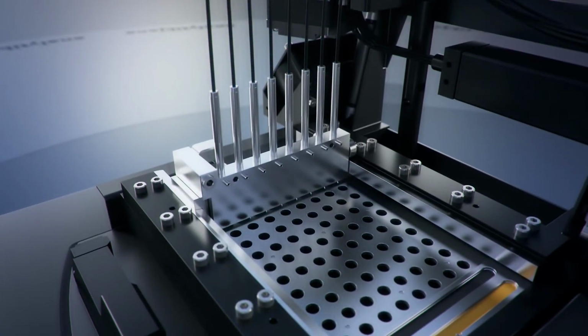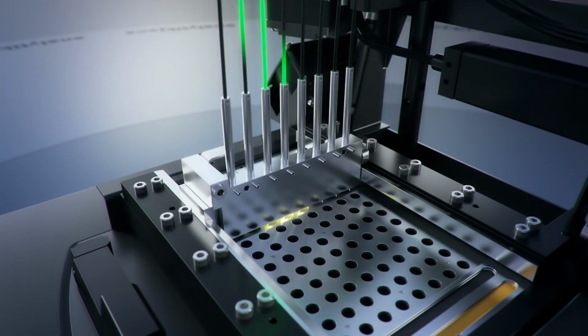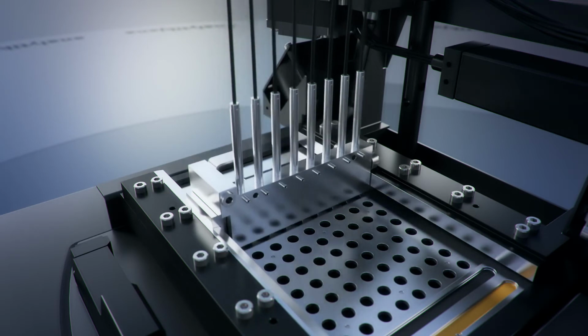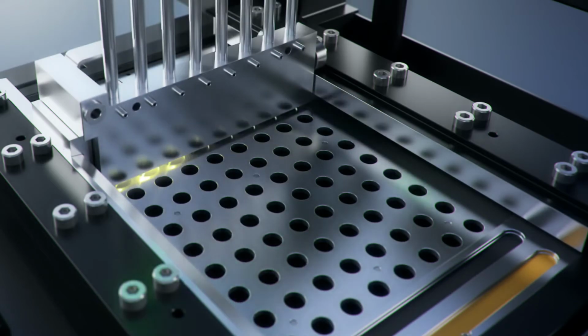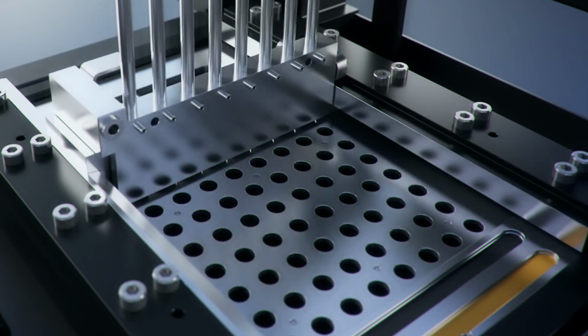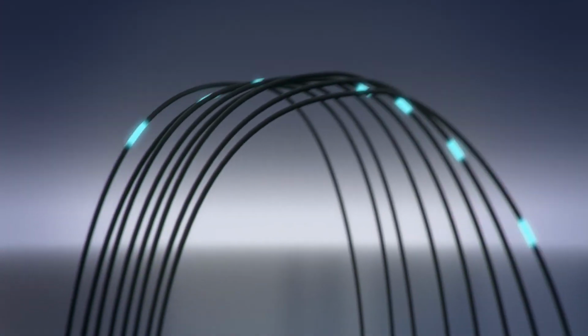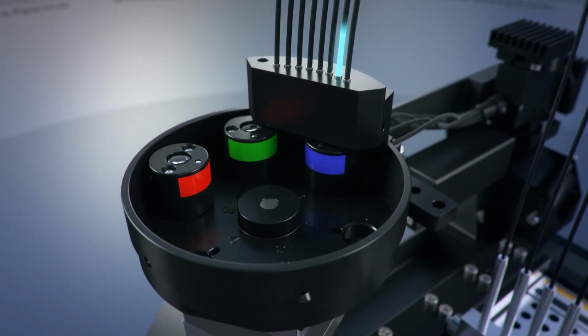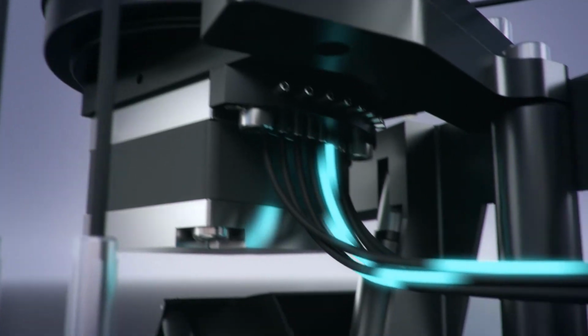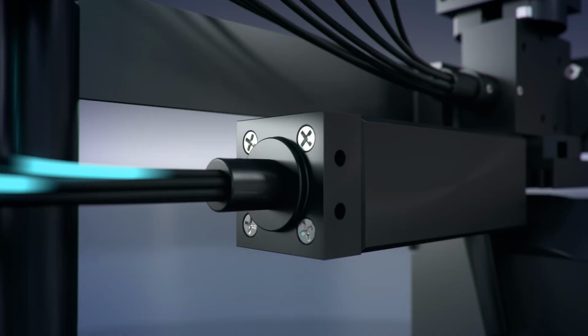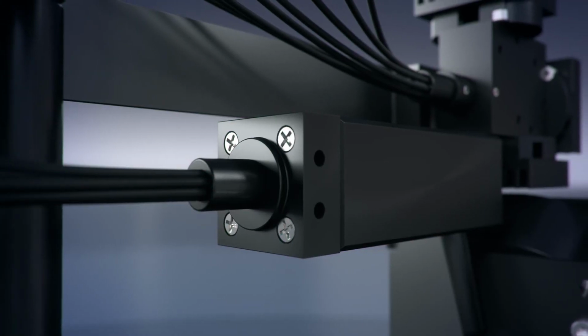Light fibers and an 8-position optical detection shuttle offer numerous advantages. Scan times are minimized to only 6 seconds, regardless of the number of measured dyes. The single detection of each well renders the need of a passive reference unnecessary, as edge effects are completely eliminated. Additionally, the highly sensitive detector is maintenance-free and requires no periodic calibration.